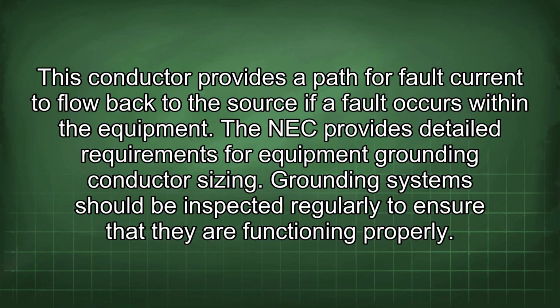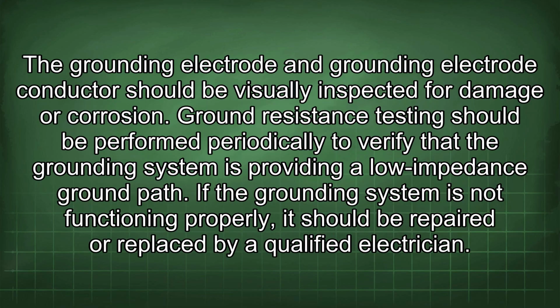Grounding systems should be inspected regularly to ensure that they are functioning properly. The grounding electrode and grounding electrode conductor should be visually inspected for damage or corrosion. Ground resistance testing should be performed periodically to verify that the grounding system is providing a low impedance ground path. If the grounding system is not functioning properly, it should be repaired or replaced by a qualified electrician.